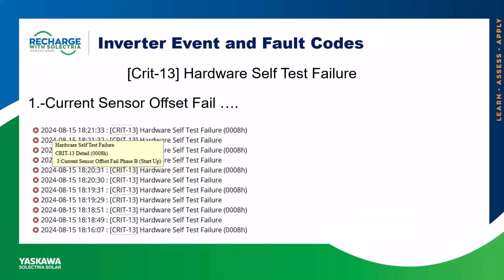As I mentioned, typically you'll see the warn 4 tied with a crit 13, and if you hover over the crit 13 fault, as you can see in the picture, it says current sensor offset fail phase B on startup. So that means that this phase B CT is not functioning properly and is what's causing the unit to fault out.